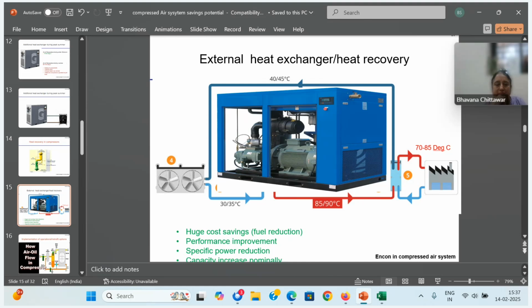So you check the capacity of the compressor either by flow meter, if there is one, or by the receiver filling method. And after replacing the oil during servicing, you check. There will be a reduction. Most of you may not be knowing this. This is an observation. I also learned this because after servicing, all of a sudden some clients were running more compressors. Once for AMC, people will come at a time and service 10 compressors. Then you notice that after oil replacement, more compressors are being operated. So we studied and we found out this is the reason.